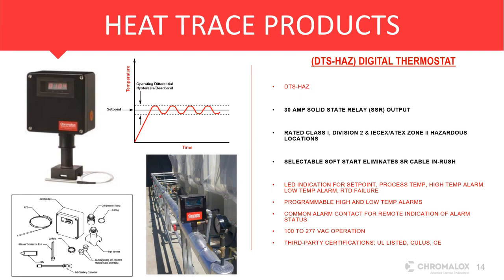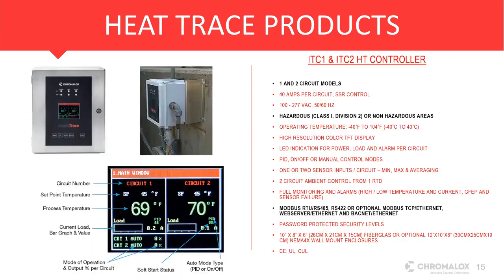From there, we obviously build up. We have a universal design to our control panels. We have the single and dual loop controllers. These are on the shelf, and we'll show you here in a second. You can have these tomorrow if you need them. In that case, there's a nice HMI that is universal on all of these panel controllers, where you have your set point, your maintenance temperature, but you also have the ability to have current monitoring integral to the unit. It's just an add-on that comes with it.